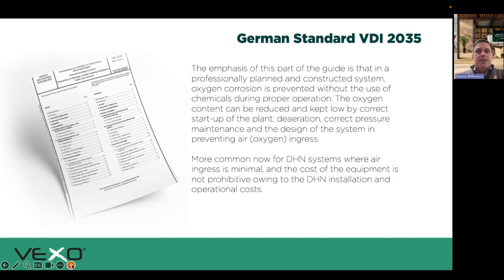The German VDI doesn't rely on chemistry or adding chemicals—it relies on removing oxygen from the water. If you remove the oxygen, you don't have corrosion. What makes water more corrosive? Obviously oxygen, but also the conductivity of the water. If we had, say, demineralized water with very low conductivity and started adding chemicals, we'd see conductivity increase, but we've got inhibitors that mitigate the corrosion risk from that. With the VDI standard, they take the oxygen out and remove some of the mineral content—not all of it, because otherwise you'd get leaching of brass fittings, etc. So it's normally about 100 or less, 50 to 100 microsiemens.